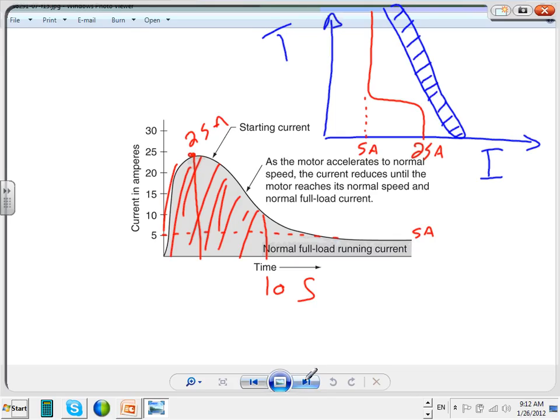This is my fuse, and on this side I have an overload. Look what they do, they work together. They have an overload protection. So this one is my fuse. This one is my overload. And the red one here is the motor start curve. Motor start and run curve, the motor curve they call it. So this is how they protect them, guys. When the motor starts, look at how the fuse is pushed all the way back. It allows the motor to start up to 25. But if the motor stalls and keeps pushing to 25, at one point the fuse is going to wake up because it's going to think it's a short circuit. If it doesn't start, it's jammed.